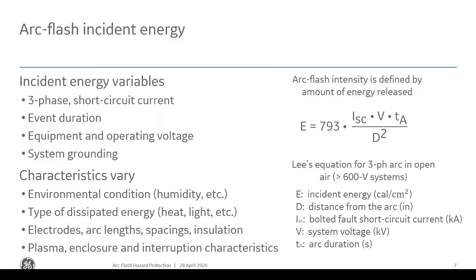So the incident energy varies: the larger the short circuit current, the higher the energy, and the higher the operating voltage, the higher the energy. The system grounding is very important too. If the energy does not have a good path to ground, that can create more energy for the arc flash, or lingering energy. And the characteristics will vary by environment, the type of energy that it dissipates, the conductor spacing, insulation, the distance that you are away from the arc flash, the enclosure, and obviously the interrupting characteristics of your relay and your breaker. We'll go through a lot of these as we go through the presentation.